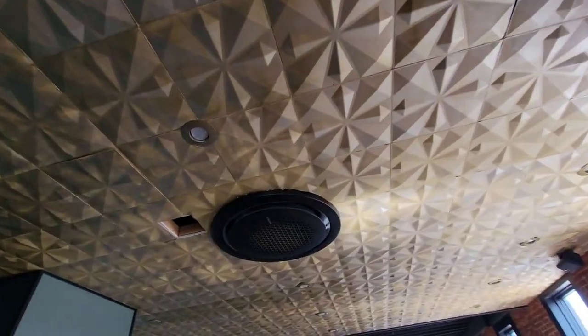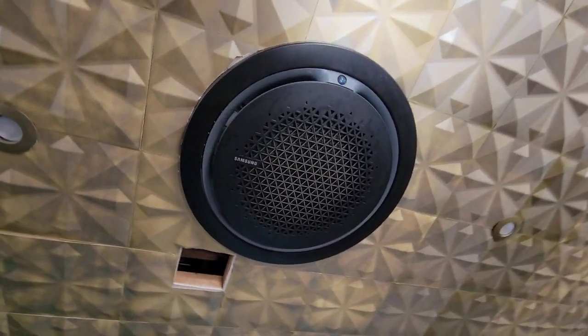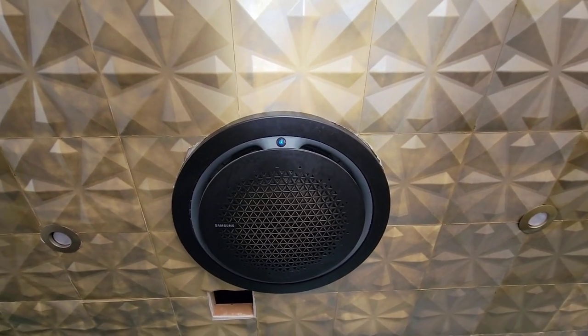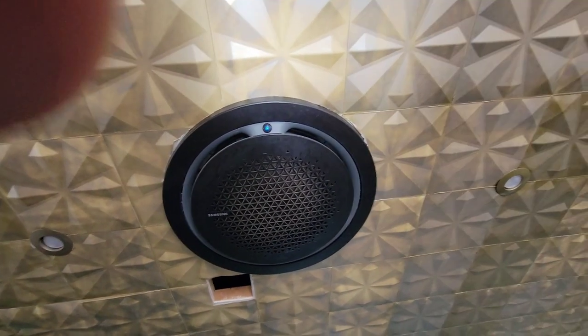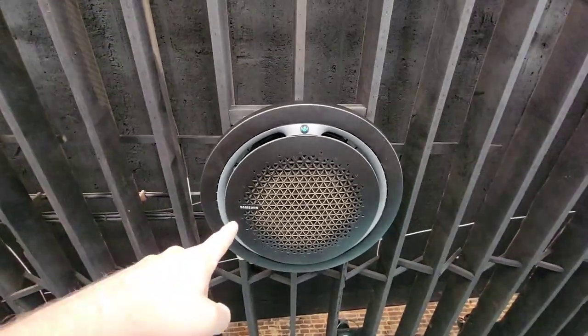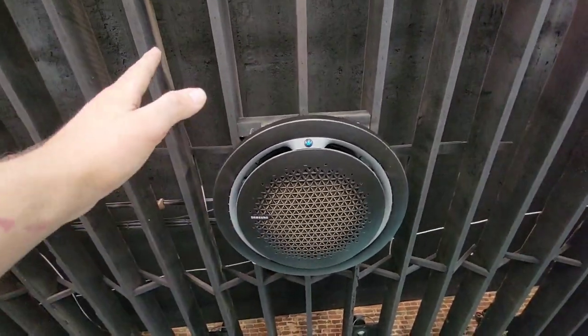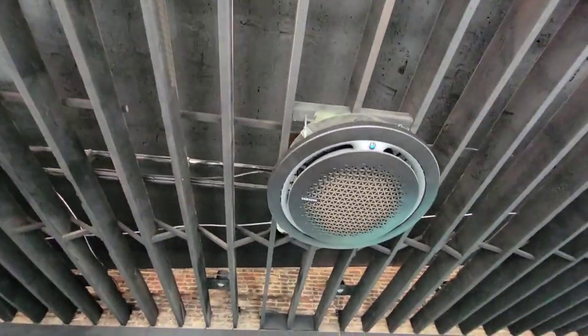I'll show you these 360 cassettes. We installed these a few years ago. Here's one cassette. Samsung. And you can see the little icon is lit up. So it's working. Let's go look at the other cassette on this unit. Remember this unit has four indoor units. You can see it's a little dirty. Needs to be cleaned. Blowing out cool air though.